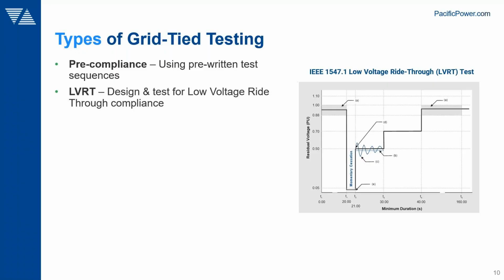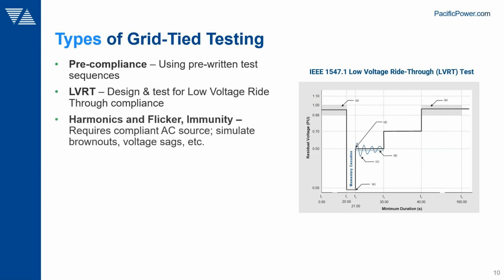For inverter types such as solar and wind, one of the many required tests is the low voltage ride through, which is the ability of the energy device to ride through a momentary power disruption or voltage sag or drop without shutting down. There are requirements for that, and this is what the LVRT test does.